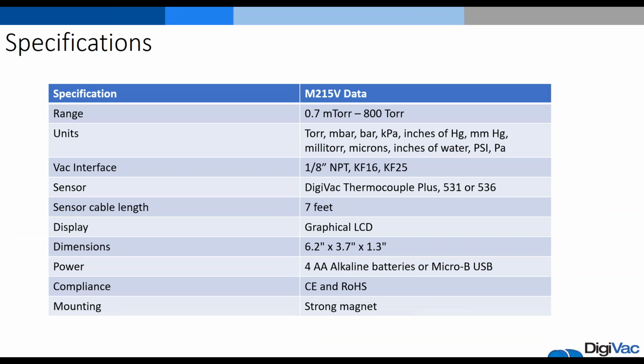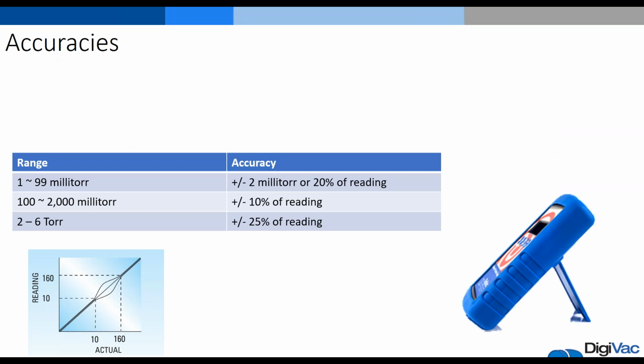So some of the specifications of the gauge are that it has 12 different measurement units, including torr, mbar, bar, kPa, inches of mercury, millimeters of mercury, millitorr, microns, inches of water, PSI, and Pa. That allows for the use of the gauge in multiple different industries and in a number of different applications. It also has CE and RoHS compliance. It has a strong magnet for mounting, which is different from most gauges. This gauge has a magnet on the back of the gauge.